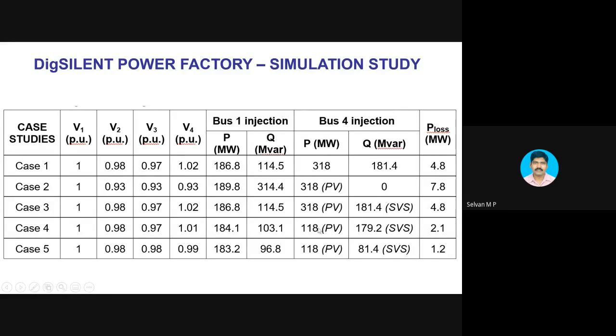And if the real power demand is reduced, real power is also reduced. Then I have to adjust the reactive power flow also. I can adjust it, because when real power transfer decreases, the reactive power requirement will also decrease. So what you have to absorb from here is, first, I need to supply reactive power at the sources where real power is generated. Second, I need a reactive power source which is capable of adjusting its output. If the real power output changes, I need to adjust the reactive power also.